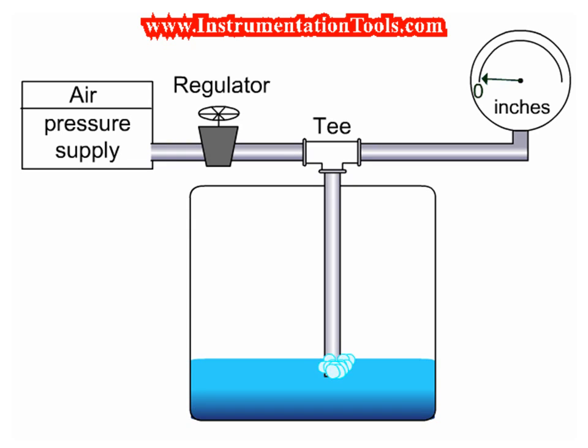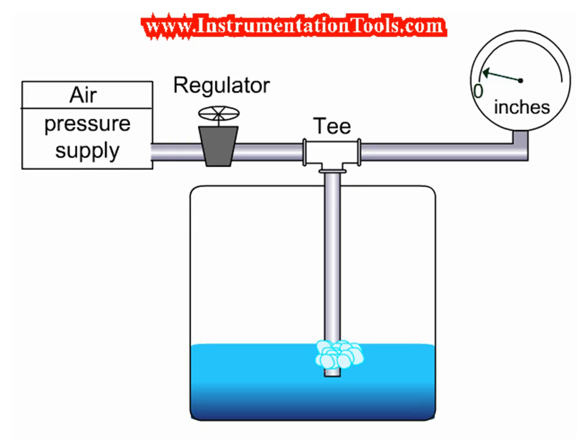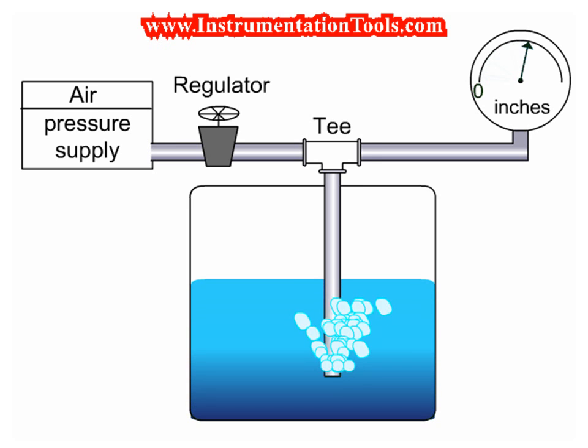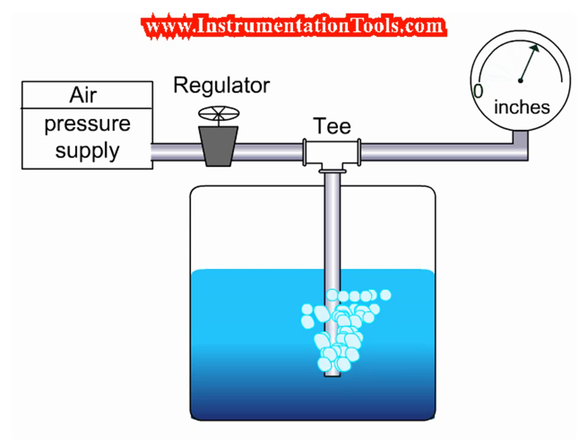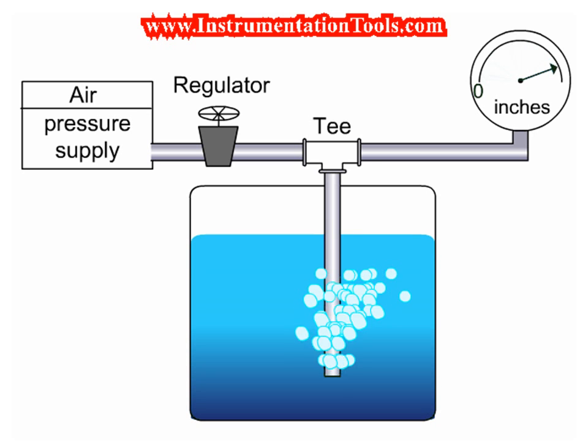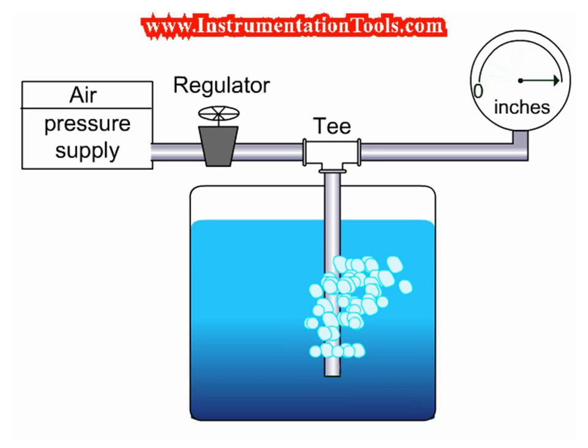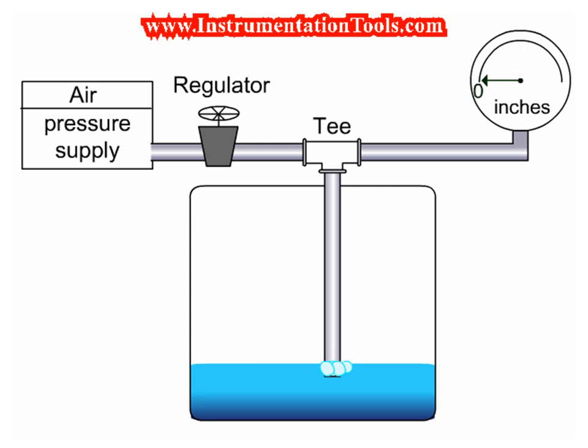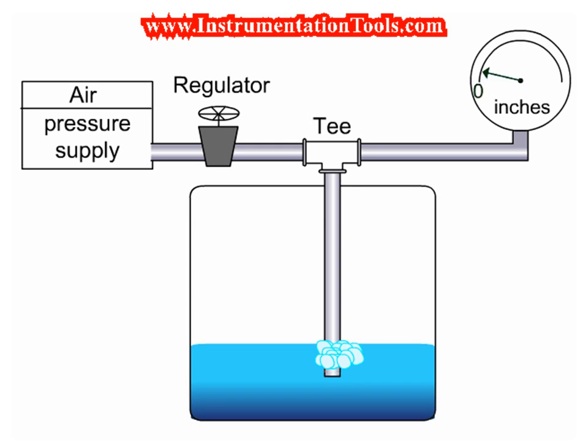Bubbler Level Measurement Working Principle. A fixed constant air supply is given at the inlet. When there is no level in the tank, total air passes to the atmosphere through the pipe in the tank. When the level in the tank increases, proportional back pressure increases, and the increased back pressure is proportional to the level in the tank.